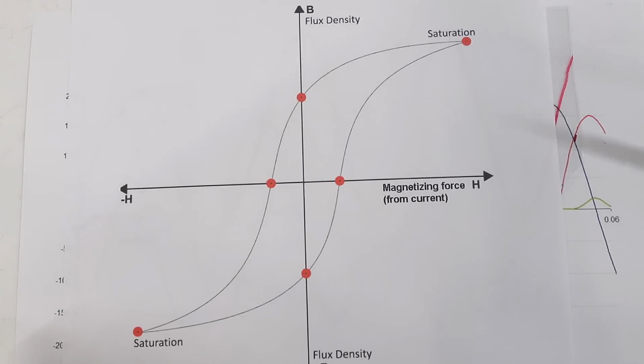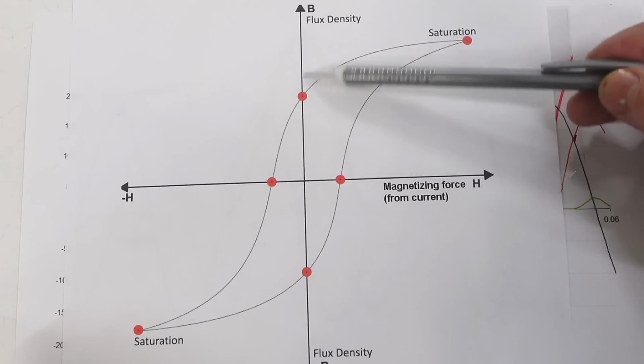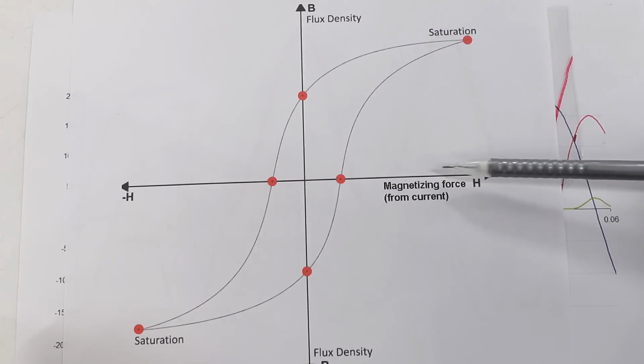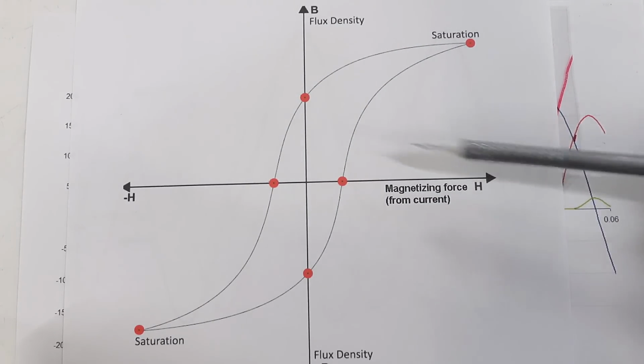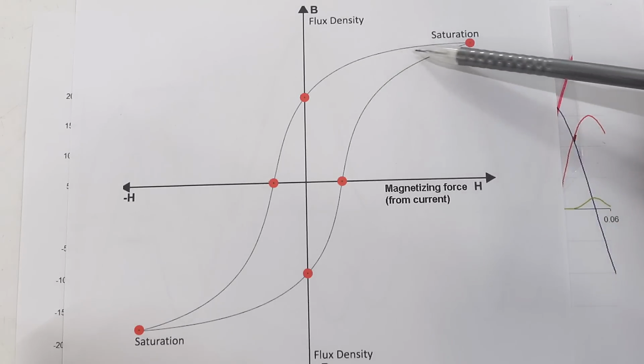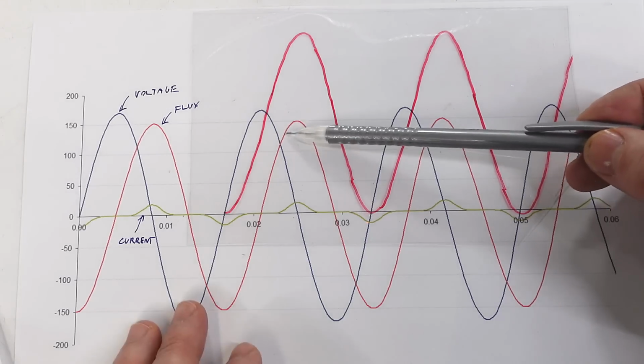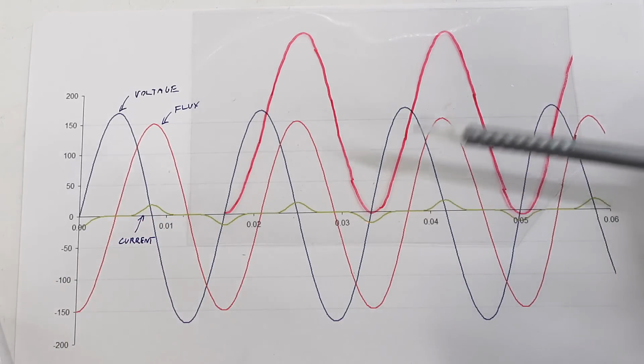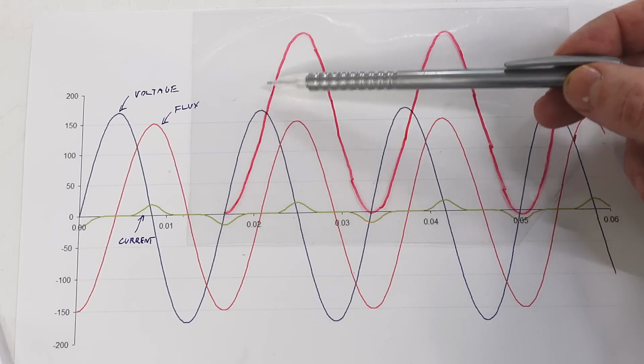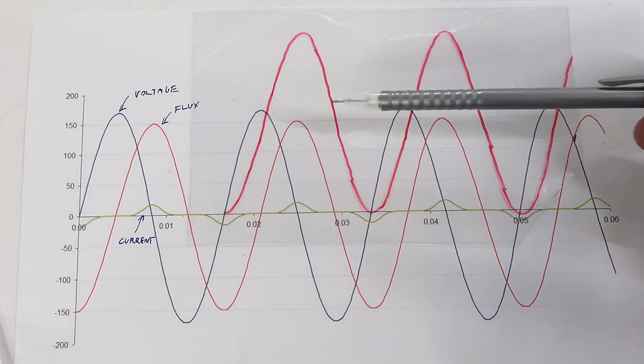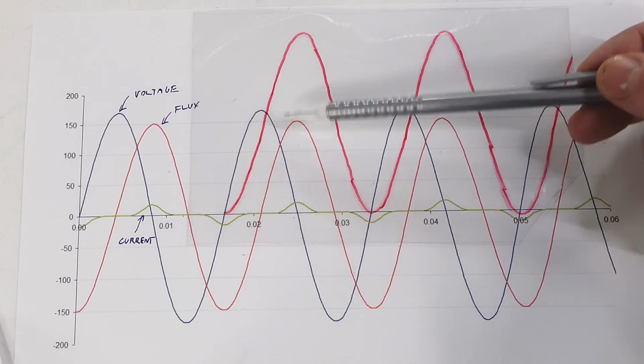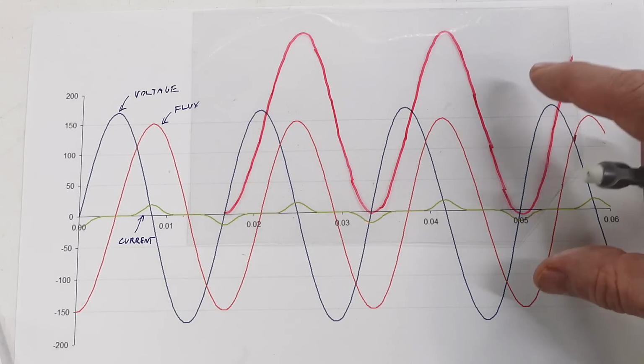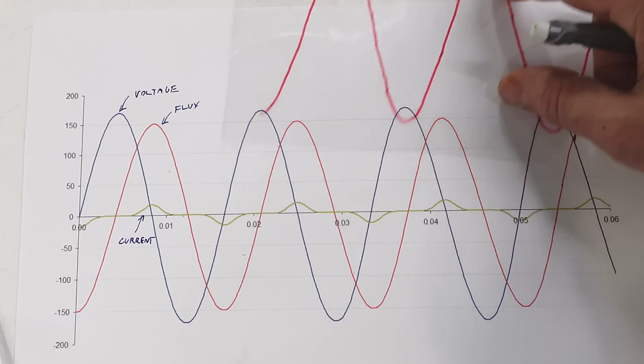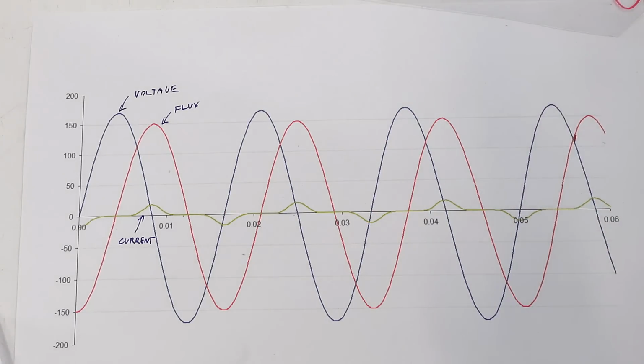If we look at a typical BH curve for a magnetic core material, the vertical axis is flux density and the horizontal is magnetizing force, which essentially comes from current. As we get closer to saturation, we need a lot more force. So as we reach peaks of flux density, we get little bumps in current because we're close to saturation. If we try to go way past saturation, the flux density won't increase any further, which means we don't take up that voltage with induction, which means we have a lot of excess voltage, turning into a lot of excess current.